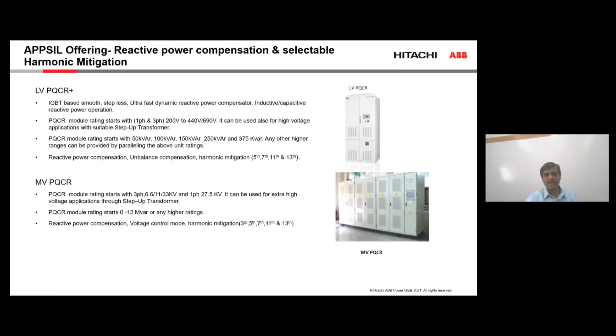I will not go through the total details of the products that we are going to use. All I'm trying to say is that we have what we know as a low voltage power quality compensator, and we have a medium voltage compensator, both of which we can use based on the network where we are connecting it. Sometimes it is wise to connect a low voltage device to a transformer. Sometimes it's wise to use a medium voltage power compensator directly on a 25 kV system. So we have various systems that are stepless, smooth, highly dynamic in nature, like the loads themselves, and they can correct reactive power, unbalance compensation, as well as harmonic mitigation, at low voltage. And these are our ones.